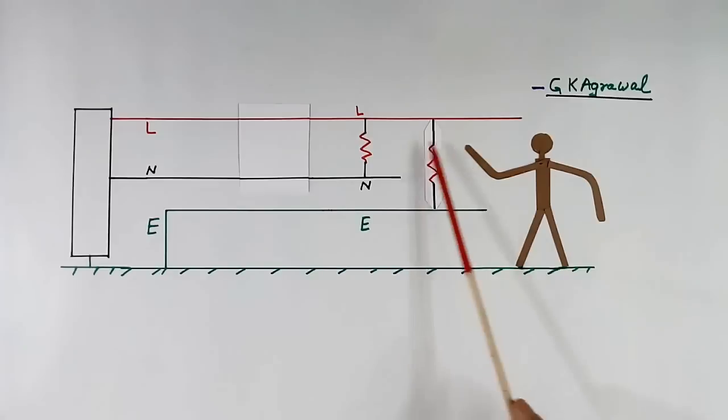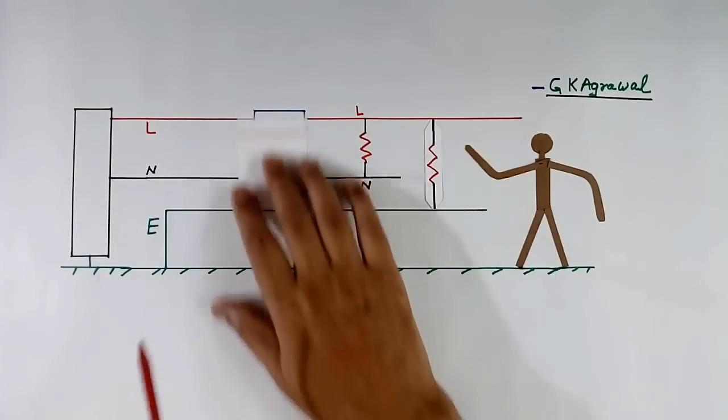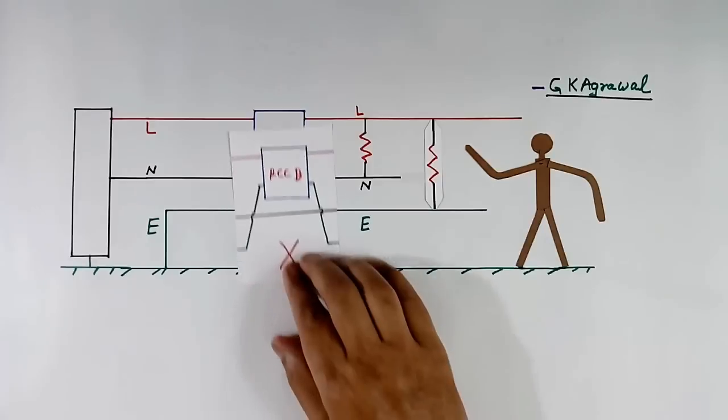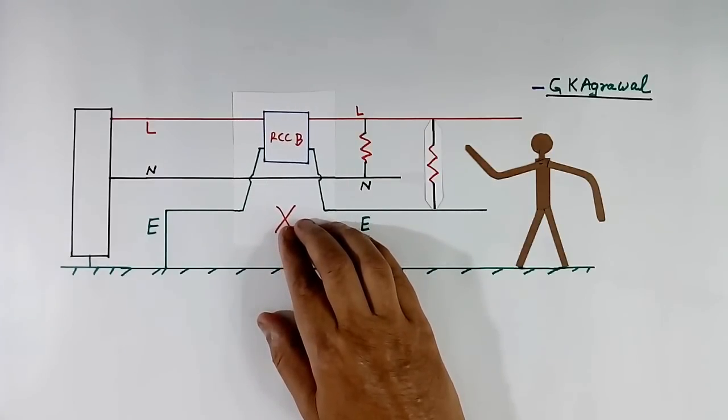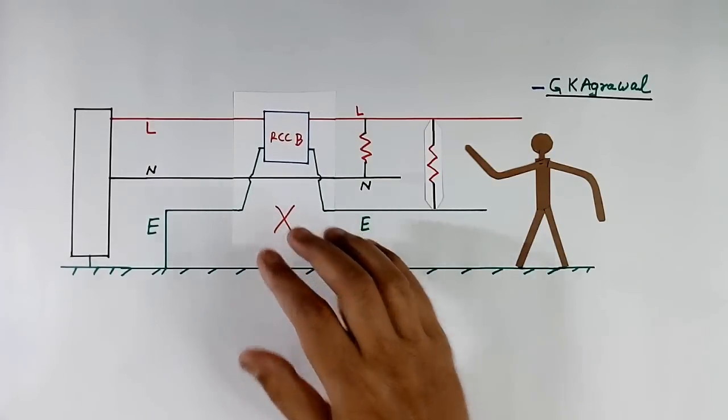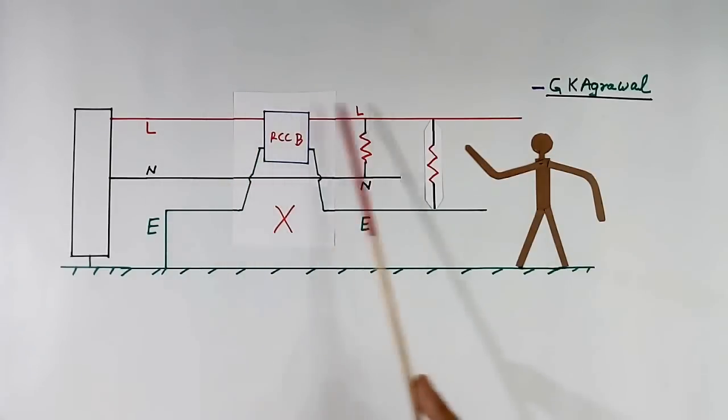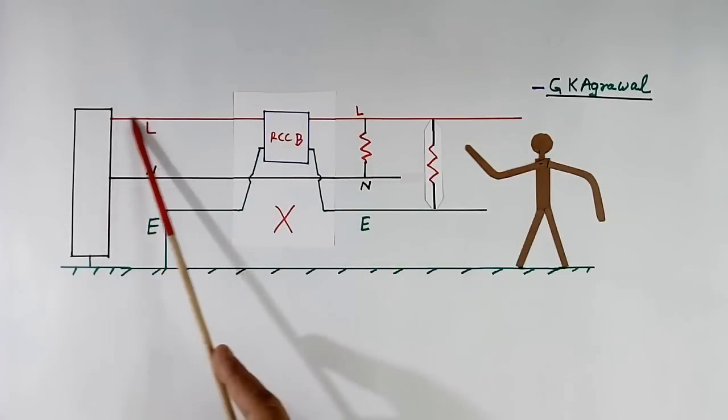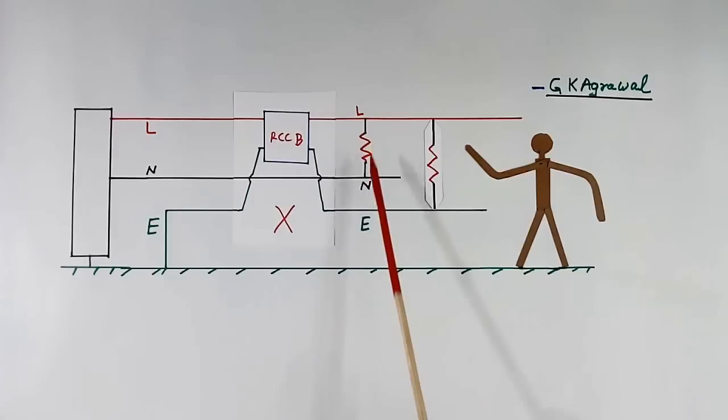Now another method to get power here is to connect RCCB like this. Now RCCB is connected between line and earth wire, green wire. But in this case what will happen? Normal load connected between line and neutral will not get any power, because current will flow like this. Whatever current is going through line will come back through neutral and will not pass through RCCB, and RCCB will trip.